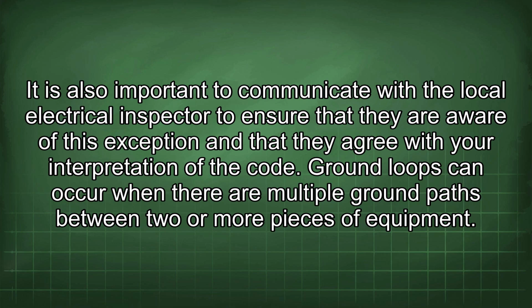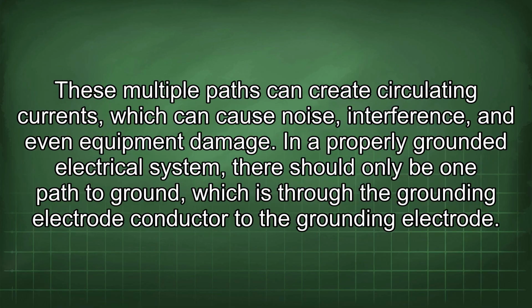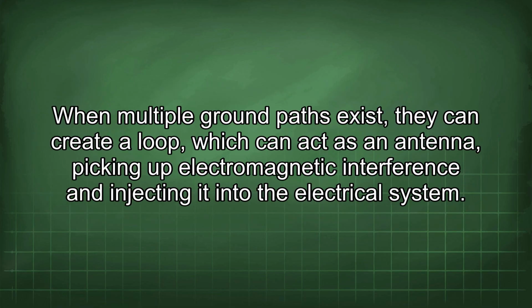Ground loops can occur when there are multiple ground paths between two or more pieces of equipment. These multiple paths can create circulating currents, which can cause noise, interference, and even equipment damage. In a properly grounded electrical system, there should only be one path to ground, which is through the grounding electrode conductor to the grounding electrode. When multiple ground paths exist, they can create a loop, which can act as an antenna, picking up electromagnetic interference and injecting it into the electrical system.